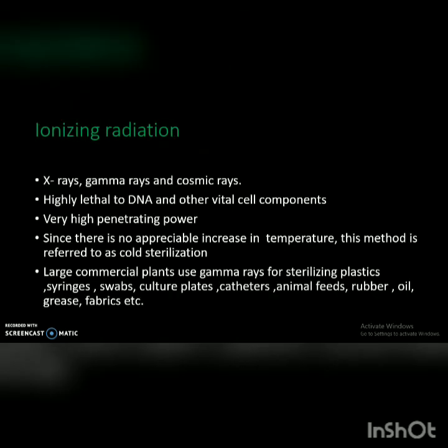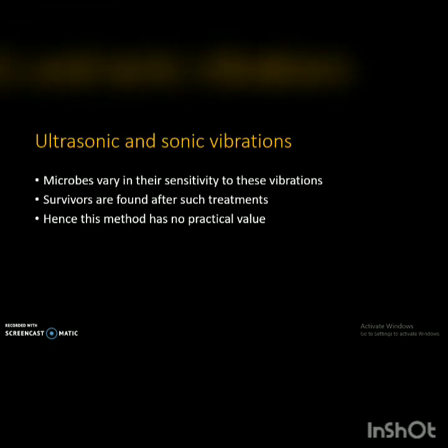Next is ionizing radiations. X-rays, gamma rays and cosmic rays can be used. They are highly lethal to the DNA and other vital cell components. They have a very high penetrating power, but there is no appreciable increase in temperature, so this method is referred to as cold sterilization. Large commercial plants are using gamma rays for sterilizing plastics, syringes, swabs, culture plates, catheters, animal feeds, rubber, oil, grease, fabrics, etc.